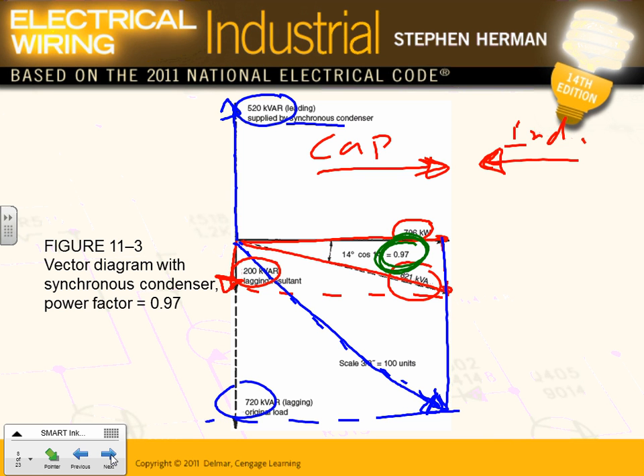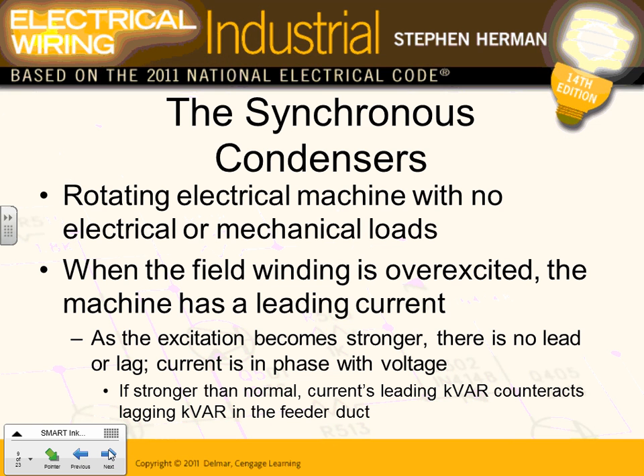Any comments, guys? Any questions? We'll take an example like this tomorrow and calculate it in detail. When you correct power factor, guys, there are two ways of doing it: adding capacitors or adding synchronous motors. Synchronous motors, guys, are a special type of motor where they put DC in the guts of the motor. By overexciting them, they start creating VARs.